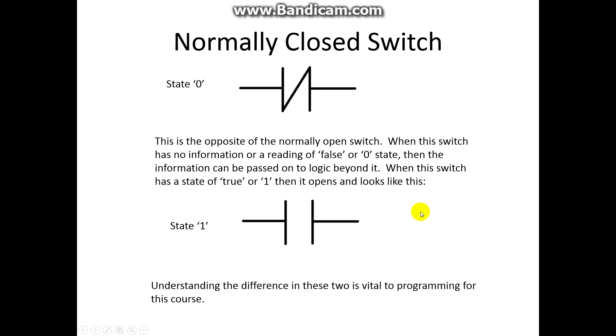Information can pass through this gate and go on to any other logic that we have. The next thing we have is called a normally closed switch. In state zero, a normally closed switch will always allow information to pass. So if there's information that needs to get through here, no problem at all. However, when we push a button or some other thing becomes true somewhere else, then this changes to an open state and no information can pass.